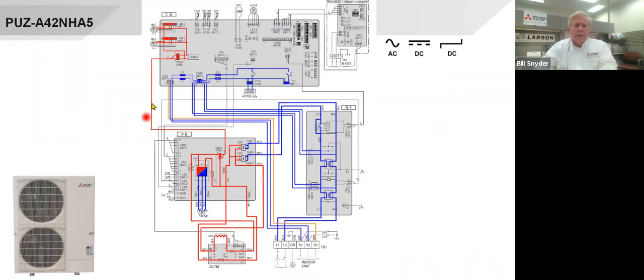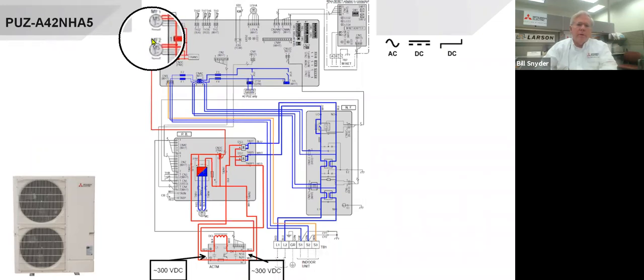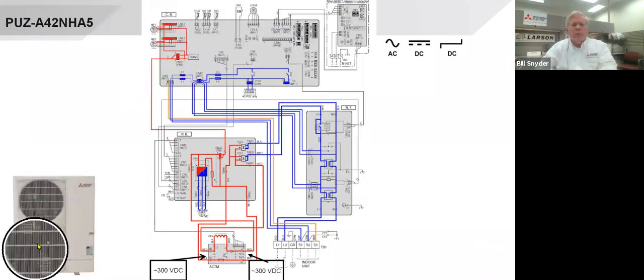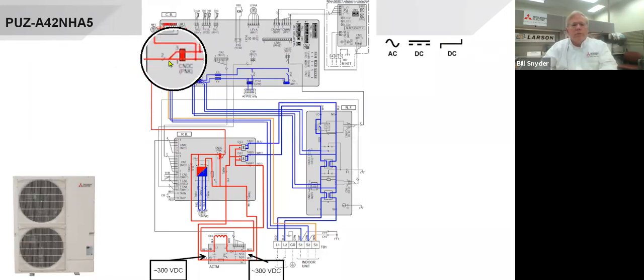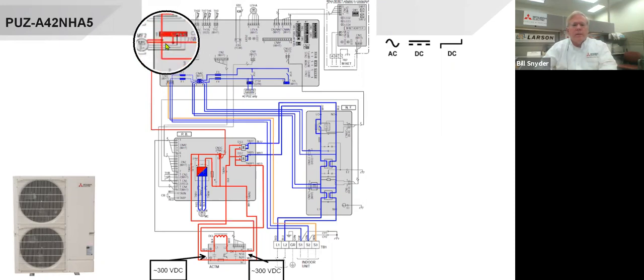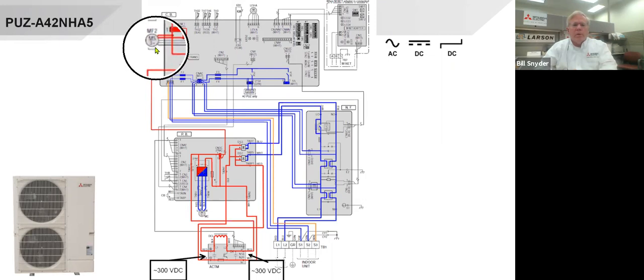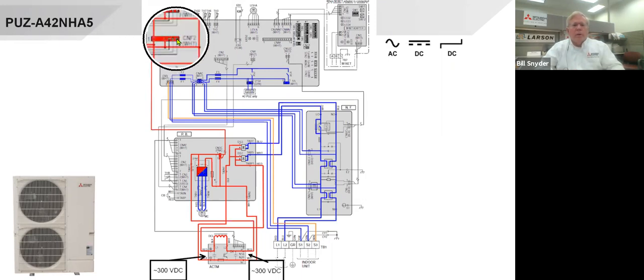Okay, so that comes up here and goes into the CNDC on the main circuit board or PC board. And again, we're separating it there as well. And then we're going out to these motors. Let's see if I can blow that up for you. Come on, right there. It says MF. MF may not be what you're thinking. It means motor fan in Mitsubishi speak. And there's motor fan 1, motor fan 2, and that's these condenser fan motors down here. But you'll notice it comes off of that CNDC and it's that red line, so that voltage is DC voltage. Don't know if you can see it, but on the fan there, let's see if I can hold my hand steady, you've got a 3-phase symbol on that fan, but we're running DC voltage to it.